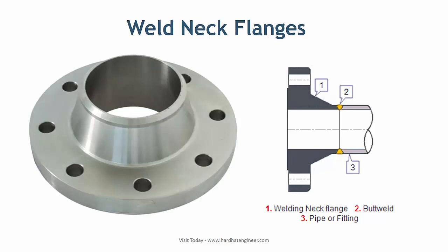Weld neck flanges are the most widely used flanges in process piping. They give the highest level of joint integrity due to the butt weld connection with the pipe. This type of flange is used in high pressure and temperature applications. Weld neck flanges are bulky and costly with respect to other types of flanges.